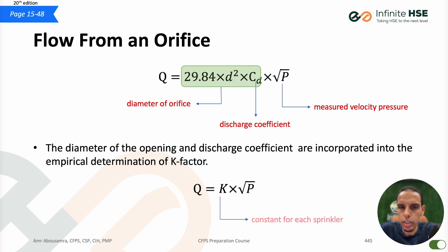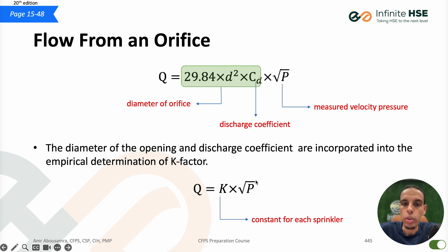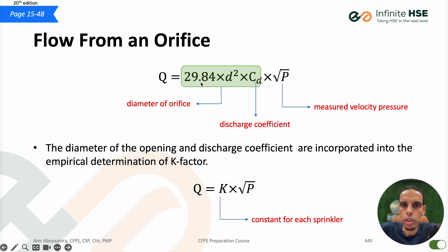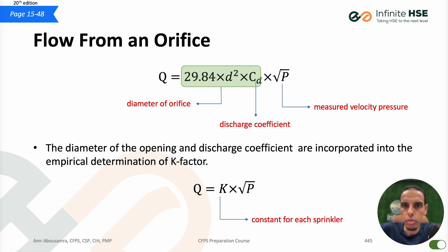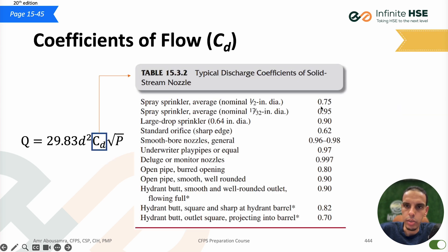This is how the k-factor is calculated. The equation becomes Q = k × √P, which is the basis for all hydraulic calculations. To verify: 29.84 × d² × cd — for a normal spray sprinkler, the diameter is half an inch, so 0.5 × 0.5 = 0.25, multiplied by 29.84, then multiplied by cd = 0.75. Multiply all these constants together and you get 5.6, which is the k-factor of the spray sprinkler.